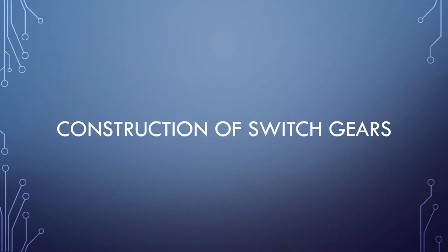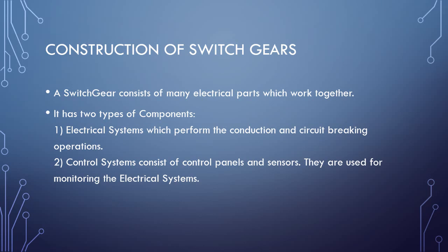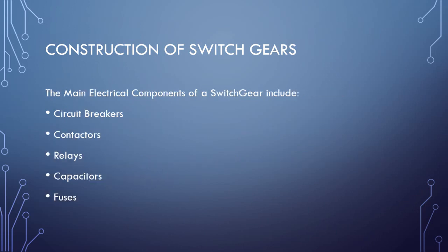Construction of switchgears. Switchgears have two types of components: electrical components and control systems. The control systems consist of control panels and sensors for monitoring and sensing of electricity and the internal electric circuitry. The control system controls the electrical components and helps protect them from damage. Displays are also included for ease in operation. The important electrical components include circuit breakers for stopping the current flow, contactors which act as conductors for switching, protection relays for smaller components inside the switchgear, capacitors for maintaining power factor and reducing the reactive power, and switch fuses for preventing any abnormally large currents.